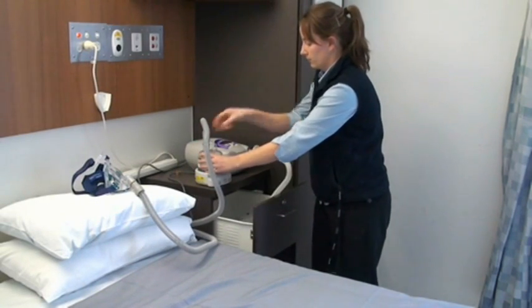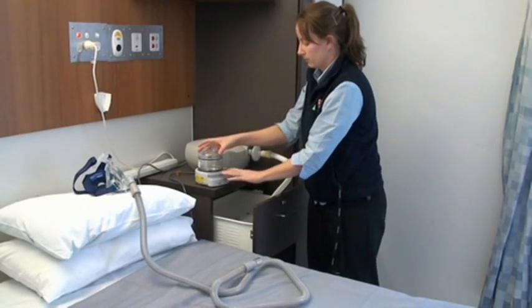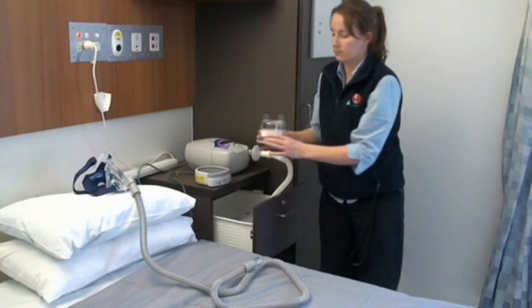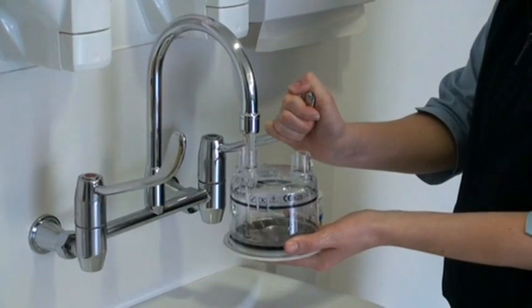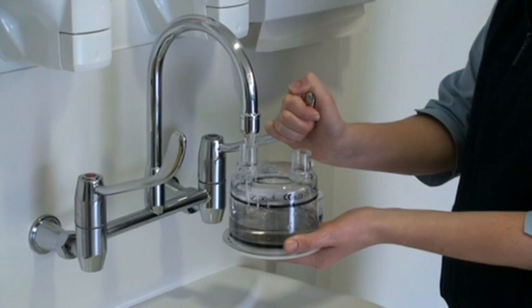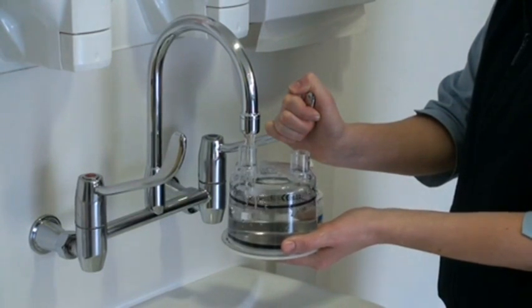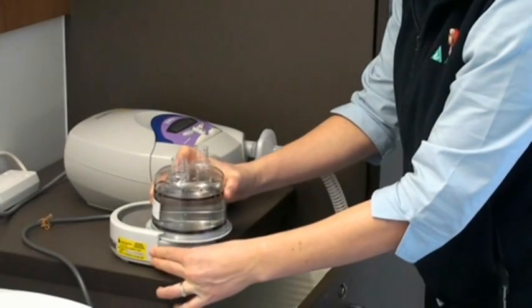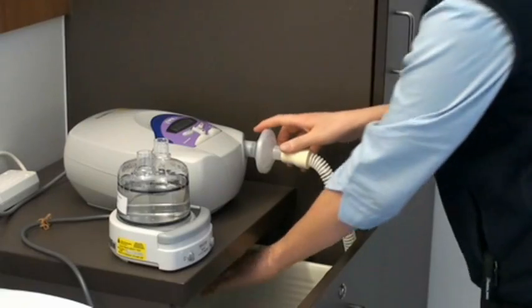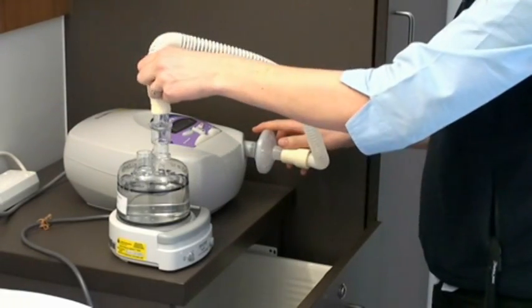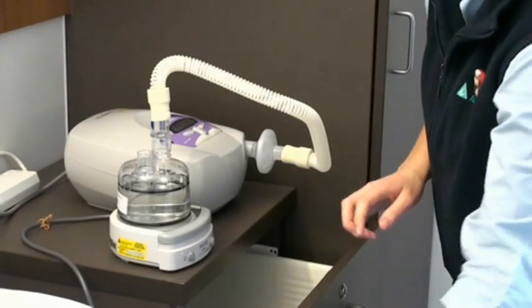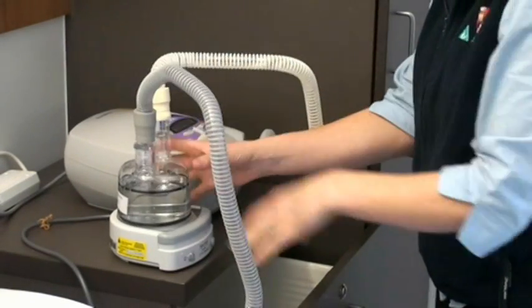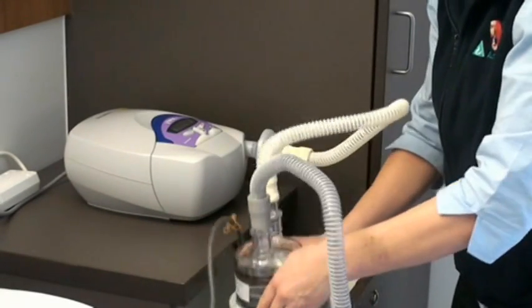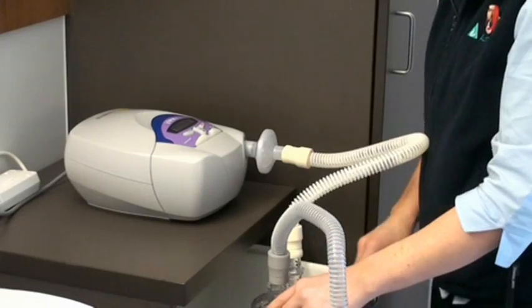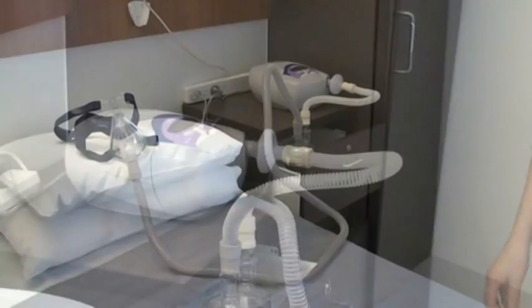Detach the humidifier chamber from the humidifier base and disconnect both breathing tubes. Fill the chamber with clean water up to the line and reattach to the humidifier base. Reconnect both breathing tubes. Turn the humidifier power button on to heat the water. There'll be a green light when it is turned on. Return the humidifier to the drawer, being careful not to spill any water. For more information on setting the temperature control, refer to your discharge education book.